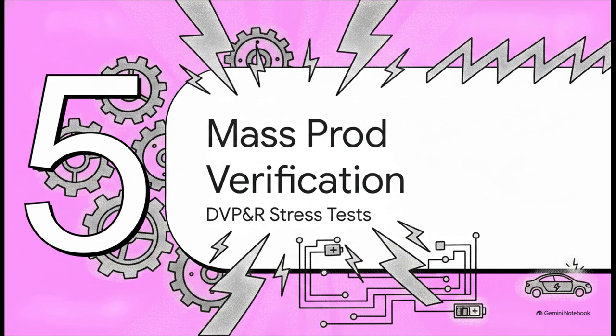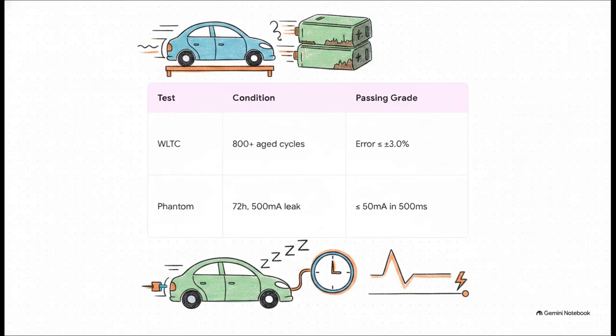And that brings us to Phase 5, DVP&R, Mass Production Verification, the ultimate stress test. Before mass production gets the green light, the stress tests they run are, honestly, intense. They take aged batteries, packs that already have over 800 cycles on them, and just torture them with a WLTC dynamic test loop at 25 degrees Celsius. To pass, the error margin has to stay strictly within plus or minus 3.0%. But the phantom load test is wild. They intentionally inject a sneaky 500 milliamp leak into a sleeping car for 72 straight hours. The passing grade? Once that car wakes up, it has exactly 500 milliseconds to spot the drift and auto-calibrate it down to a tiny 50 milliamp residual.